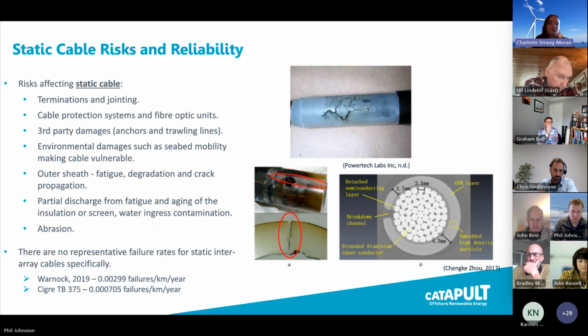There are no representative failure rates for static intra-array cables specifically. Two perhaps most used in literature would be Warnock, from 2019, that stated that 0.003 failures per kilometre per year was the failure rate for cables. This, however, focuses on export cables for the UK alone. When we look to perhaps a much better known and well recognised document, we have CIGRE Technical Brochure 375, which states 7 times 10 to the minus 4 failures per kilometre per year. However, what we have to realise with this CIGRE brochure is there was very limited information on offshore wind cables within the survey, so having that as a representation of intra-array cables is difficult to justify. Next slide, please, Phil.